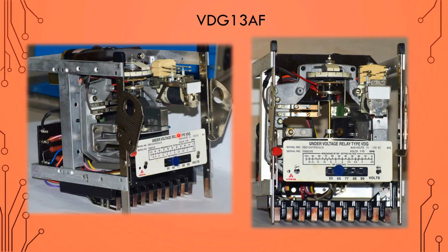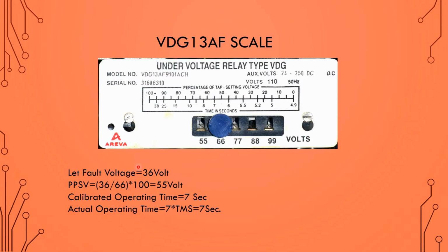And as you can see, this is the relay unit which we have taken out from the box. And right now this is the nameplate of the relay. On this nameplate, if you see, the model number is VDG13AF relay, and its auxiliary is 24 to 250 volt DC. A wide range of auxiliary voltage options are available, and the voltage rating is 110 volt at 50 hertz.